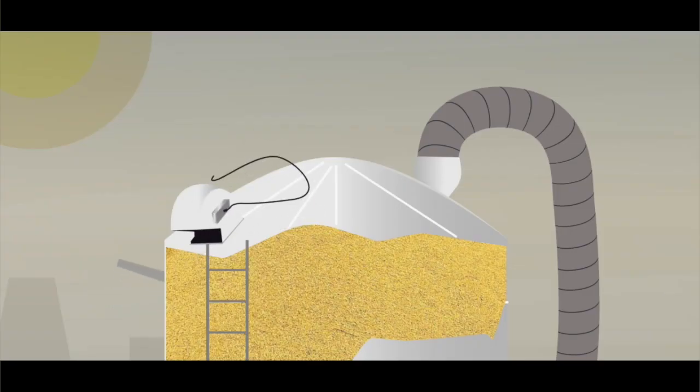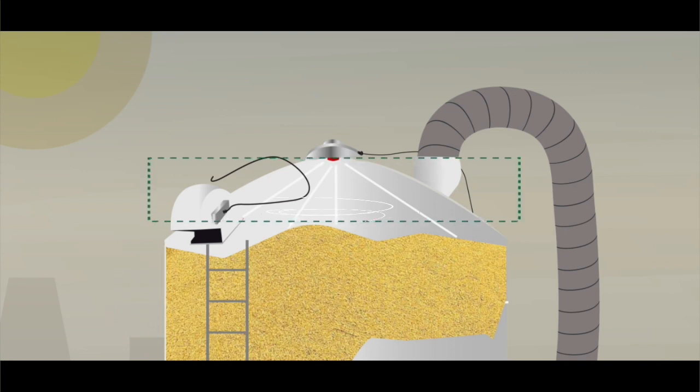With a humidity sensor on the exhaust air and temperature sensor on the roof of the silo, we can control the relative humidity and ensure that the dew point inside the silo never rises to the temperature of the silo roof.